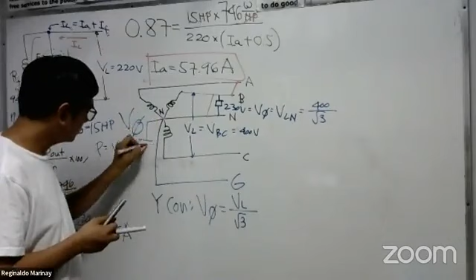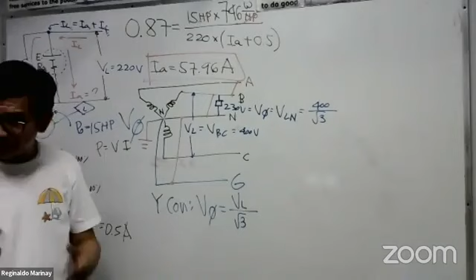Okay? Fault current between neutral and ground. Okay. I will put a short-circuiting conductor between neutral and ground here. Question. Are they shorted? Okay. Electrically, are they shorted? Yes or no? Take a look here. This is your neutral. This is your ground. Are they shorted? The answer is no. They are not shorted. Why? Because they are already shorted. They are already connected here. You see?